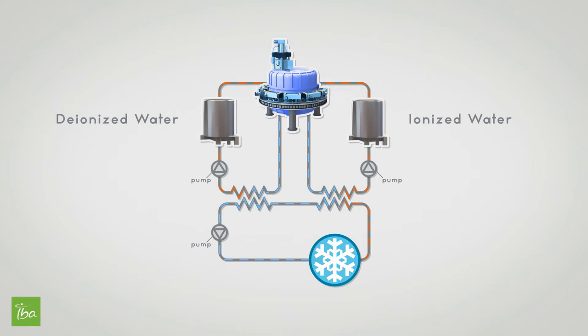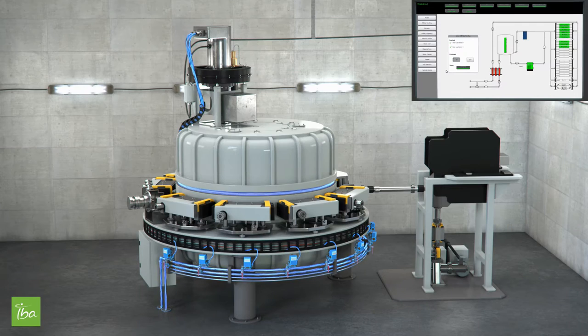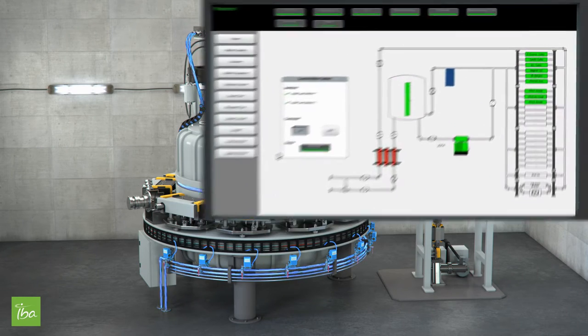The water of these two closed circuits is cooled down by a chiller or an equivalent system. The heat exchanger dissipates the heat of each subsystem through the water cooled by the second cooling system. The cold water of this closed circuit is then distributed all over the machine on each subsystem.